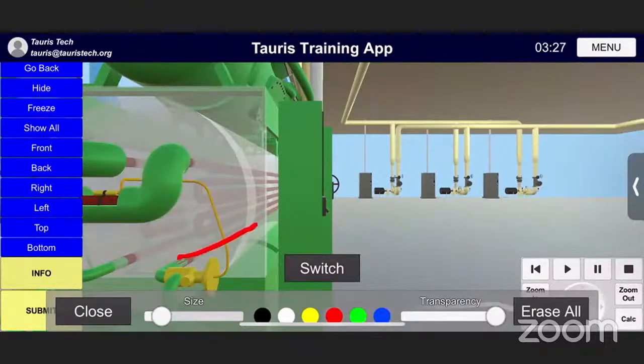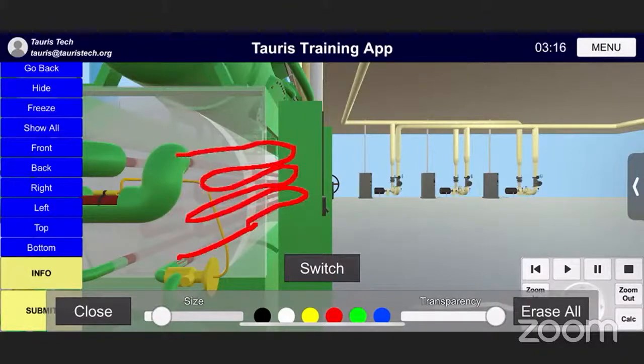If you look here, this is my TEV that feeds into my coil. It's the same thing we have here. Our coil is going around like that, and now it's coming out of our suction line. We just checked our pressure, right? It said 35. So I'm boiling at 35. That's what I use the pressure for.